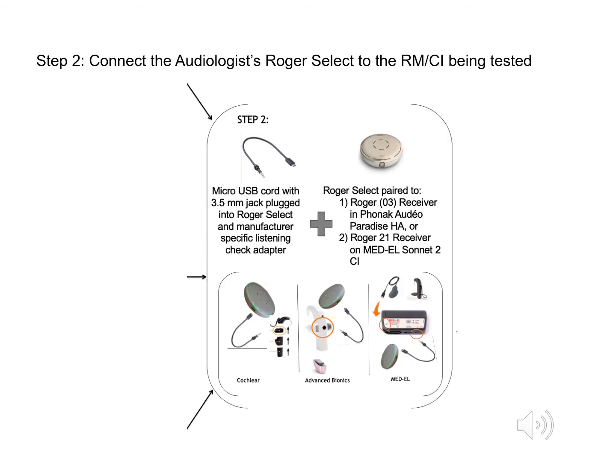Step 2 connected the Audiologist Roger Select to the remote microphone cochlear implant being tested. Each manufacturer's specific listening checker comes with removable earbuds that have a 3.5mm cord on them. We plugged a 3.5mm jack into the auxiliary jack with a micro USB port on the opposite end. The micro USB cord was plugged into the Roger Select directly. At the bottom, you can see each illustration for each manufacturer that this entailed.